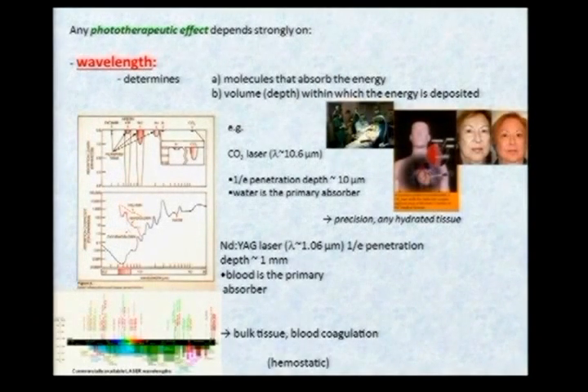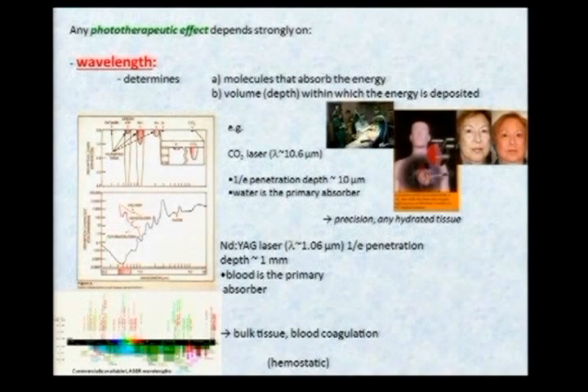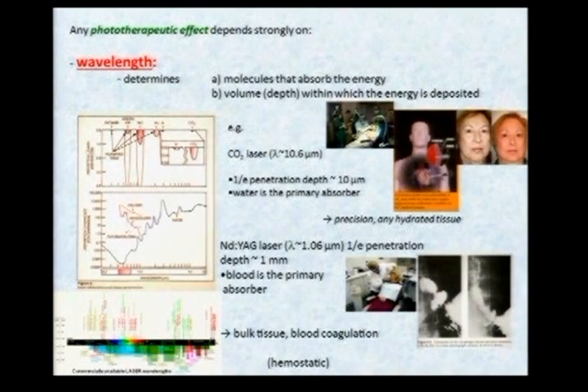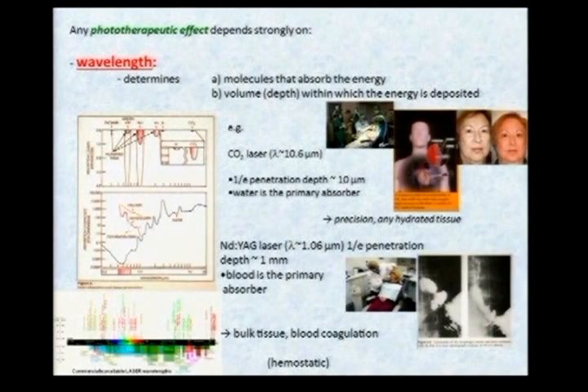At the other end of the scale, coming down a factor of 10 in wavelength, the 1/e penetration is more like millimeters with blood as the primary absorber, allowing bulk tissue and blood coagulation — it's hemostatic. If you tried to cut through a vascularized lesion with a CO2 laser you'd have blood spouting, but with a Nd:YAG laser, absorbed by blood, you coagulate as you cut. This is used in dentistry and, for example, to open an esophagus obstructed by tumor — going down with an optical fiber through an endoscope and burning your way through.